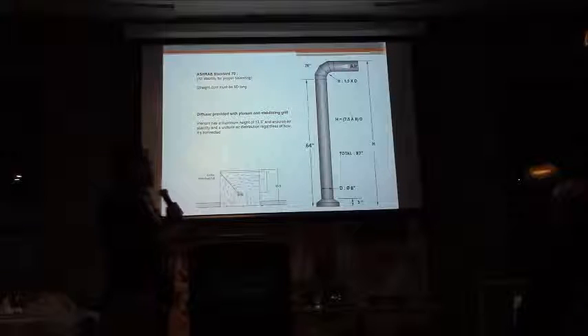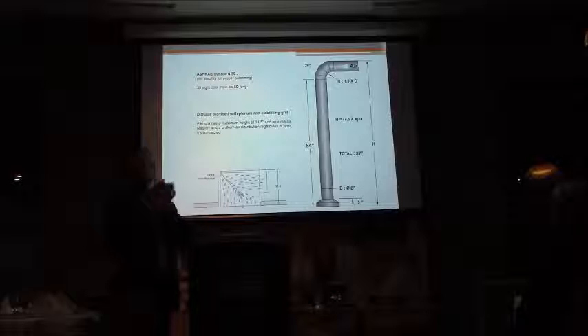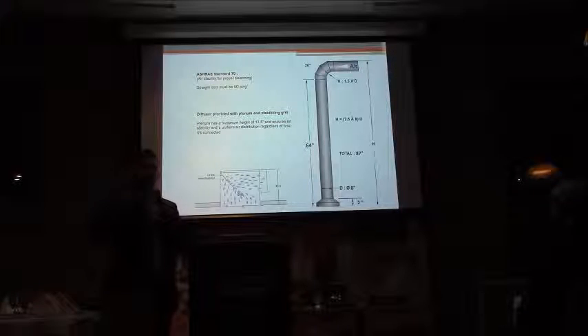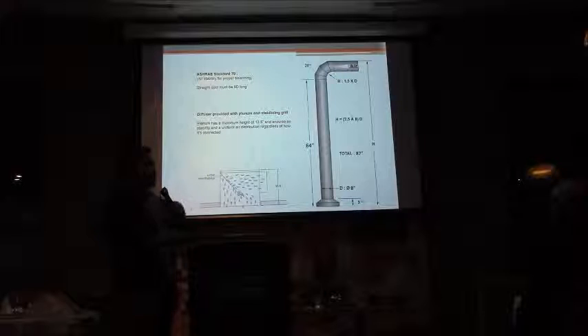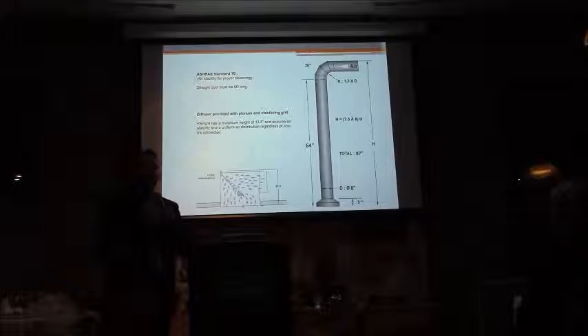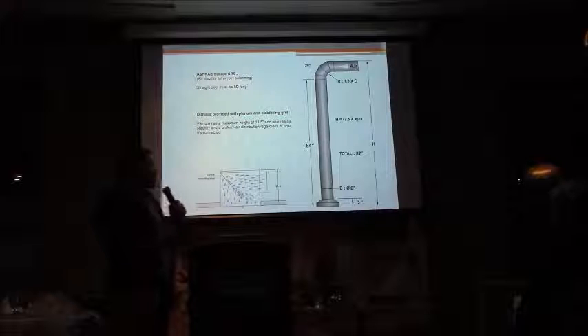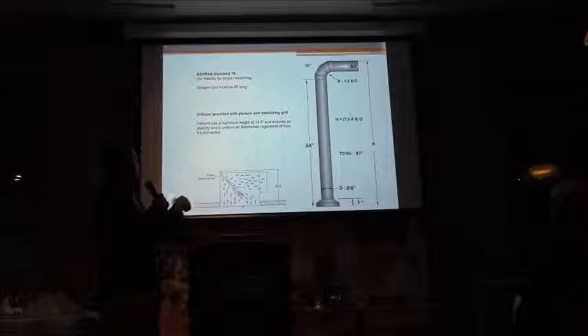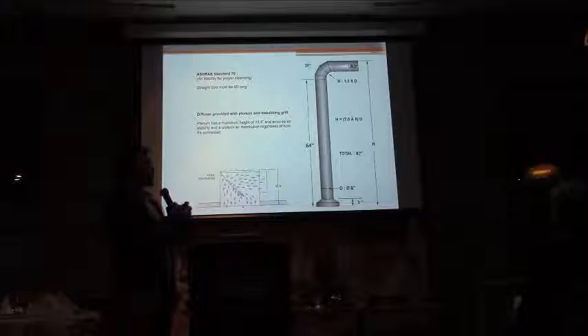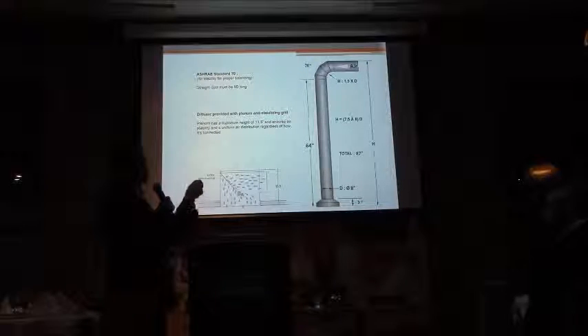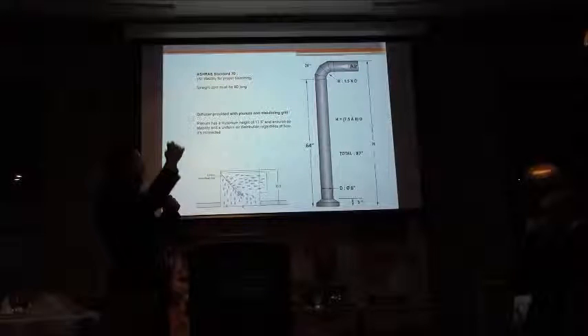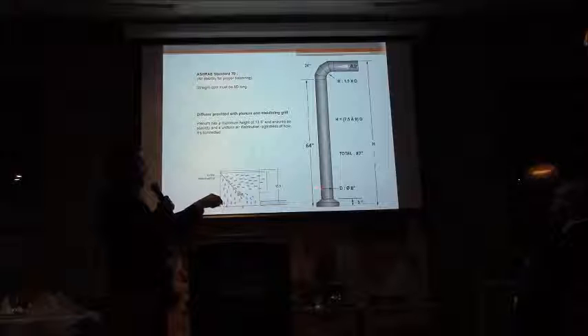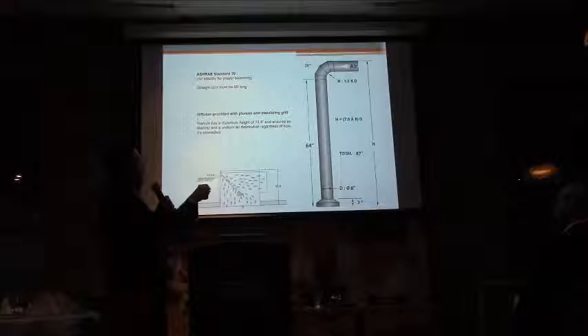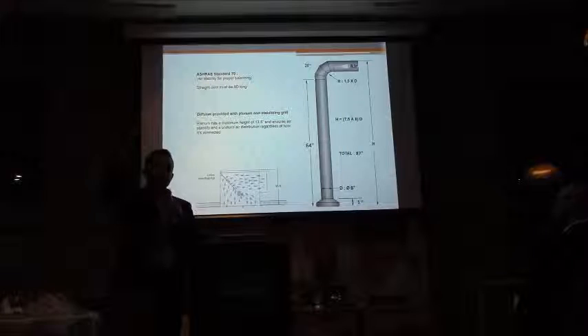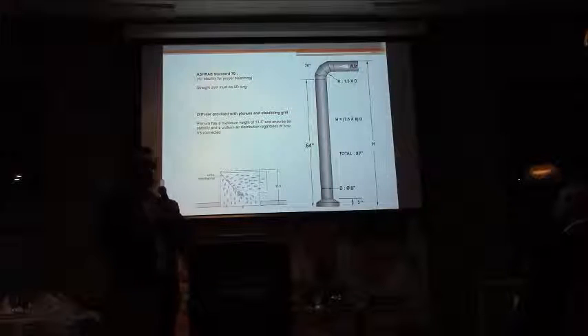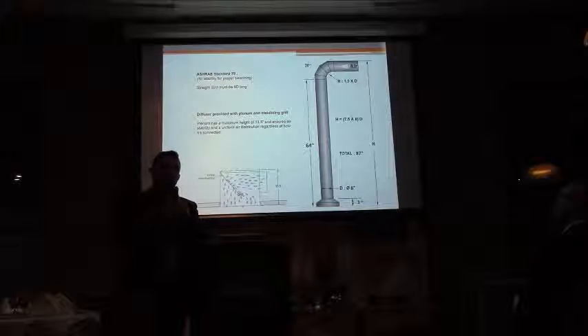So, the cone diffuser, I took its values from manufacturer B, which is a North American manufacturer. There's a lot of them that produce the cone diffuser, and all North American manufacturers test their diffusers the same way. And it's based on ASHRAE standard 70, which basically allows you to test the diffuser in lab conditions, where you have 8 times the equivalent straight duct, like the equivalent diameter. So if you have an 8-inch neck, you could have 64 inches of straight duct before your diffuser. That's for an 8-inch neck. If you had a 10-inch, that would be 80 inches of straight duct before reaching the diffuser.